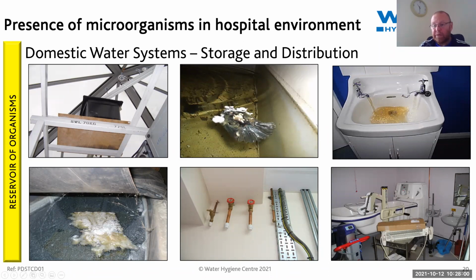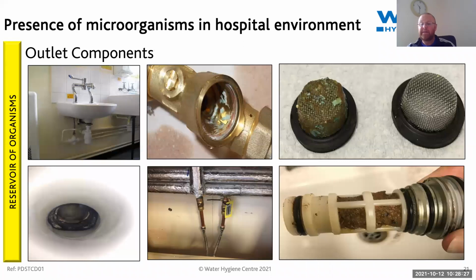Some issues with cold water storage tanks: they can be oversized, have poor turnover, be poorly configured, and could be gaining heat. Issues with hot water generators: they could be undersized, not achieving temperature, not set at the right temperature, or poorly configured. And the distribution system could have cut off ends, little used outlets, be poorly configured, or gaining heat due to lack of insulation. These are all issues we come across on a day-to-day basis.